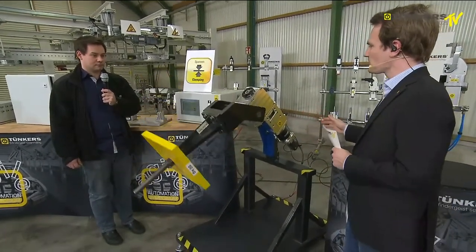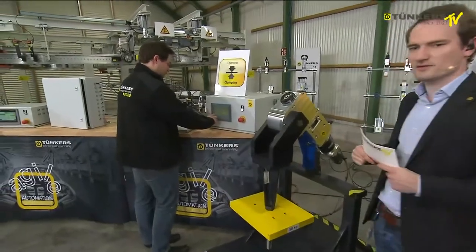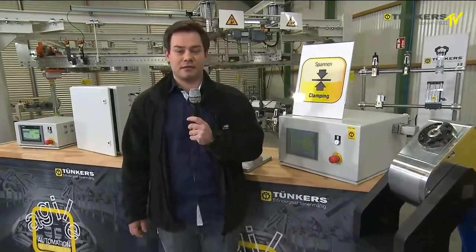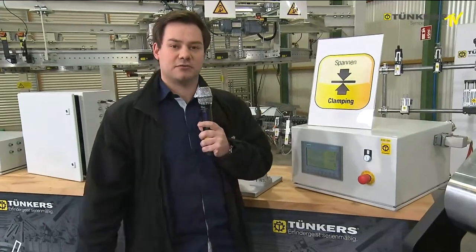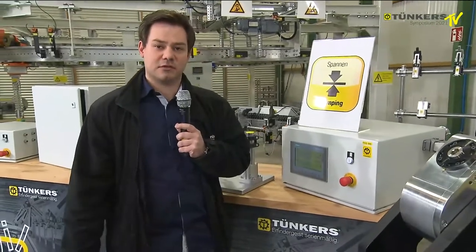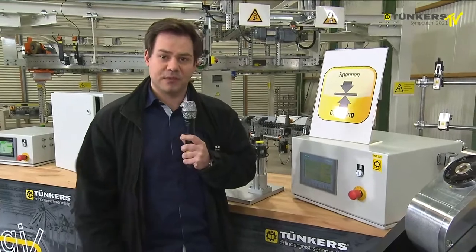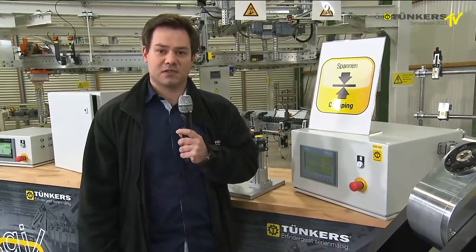With this setup, together with the control unit, we can reach a performance level D, which is necessary for many applications. To reach the performance level D, we use the S210 from Siemens, the frequency converter. In combination with this frequency converter and five safety functions, we reach performance level D. The first safety function is the SS1. It's a safe stop one.